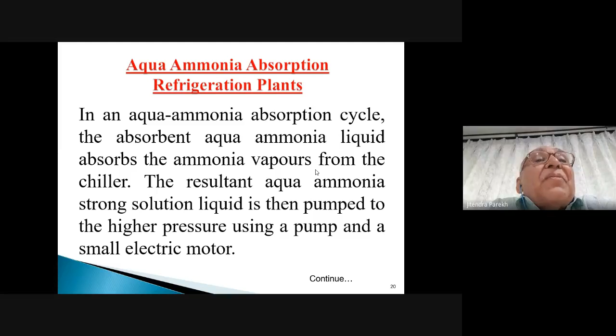Being compressible, the compression of a gas is more energy intensive compared to a liquid, which is generally incompressible. When we are talking about ammonia, the liquid ammonia system can be compressed using a pump. The high pressure liquid is then heated to release the absorbed ammonia back to the condenser. The heat is usually from steam, but in practice it can be any form of heat, and steam is generally available in our dairy plants. Next, please.